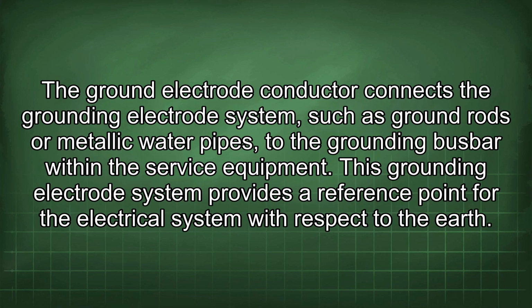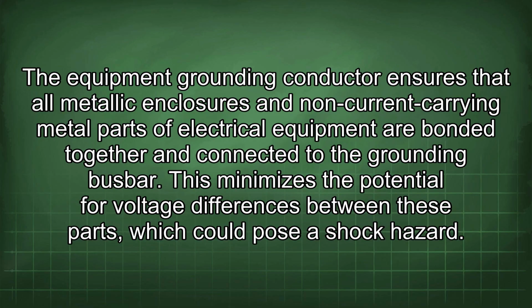The ground electrode conductor connects the grounding electrode system, such as ground rods or metallic water pipes, to the grounding busbar within the service equipment. This grounding electrode system provides a reference point for the electrical system with respect to the earth. The equipment grounding conductor ensures that all metallic enclosures and non-current carrying metal parts of electrical equipment are bonded together and connected to the grounding busbar. This minimizes the potential for voltage differences between these parts, which could pose a shock hazard.